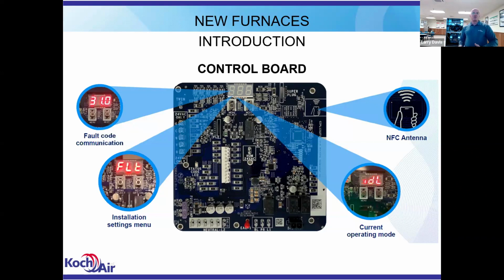These furnaces, you don't have to utilize the IntelliSense, or you don't have to use the temp sensors. That's for informational purposes only. It'll continue to operate. Factory's realized that about the fault code that pops up. It's a nuisance code, doesn't show up on the thermostat, especially if you're not using the IntelliSense thermostat. So it's just a nuisance thing that is being addressed in future boards. The fix for that is a new software version in the board.